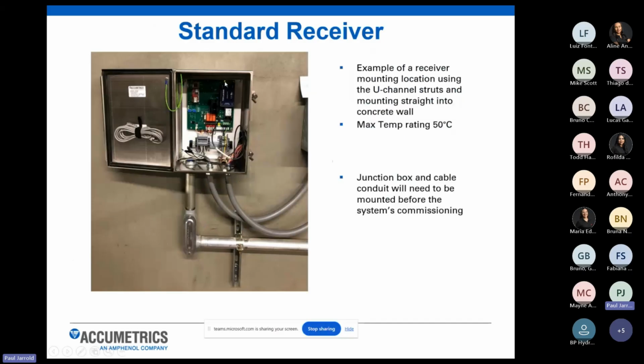We need power brought to our receiver electronics, either AC or DC power. And then we always recommend that a single conduit cable be routed just for the BNC connection for the coaxial cable to the pickup antenna. So that's what this middle conduit is. And then the larger conduit on the left is your outputs, your 3 relay contact outputs, as well as your 4 to 20 current loop analog outputs would be routed back to the control room.